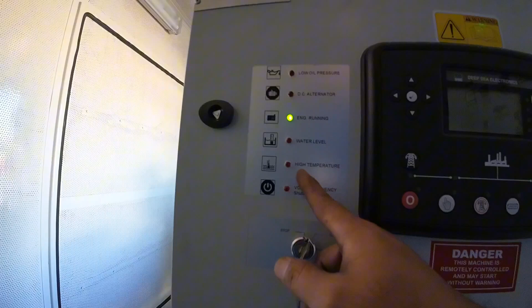Since the deep sea controller is not working, you have no monitoring at all. Here you can see the frequency and voltage from your generator. If there are any shutdown alarms or malfunctions of the engine, you can see low oil pressure, DC alternator, low water level, high coolant temperature, frequency and voltage, and you can see the alarm if there's any failure.